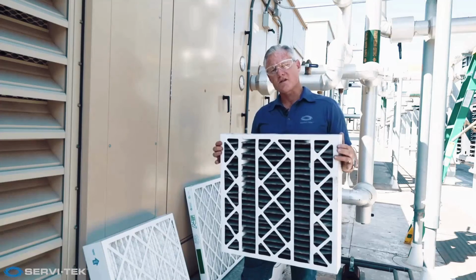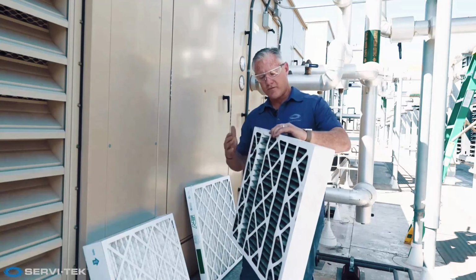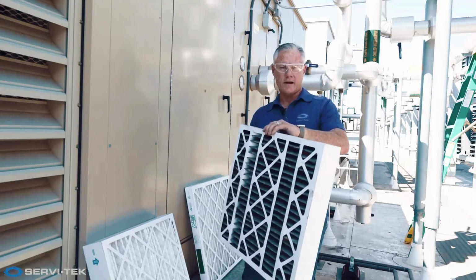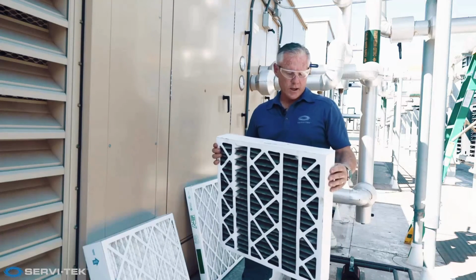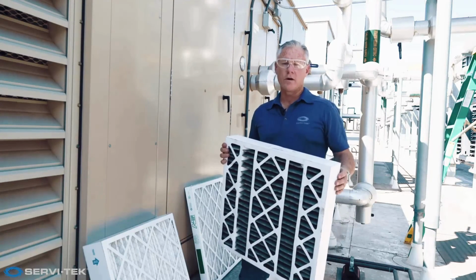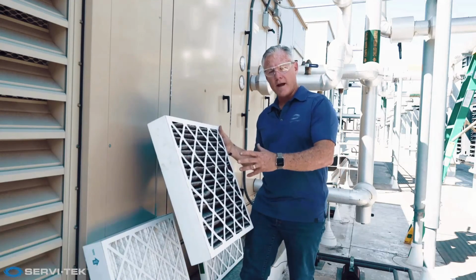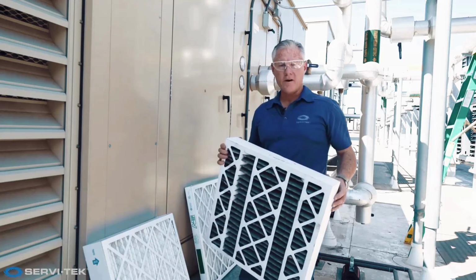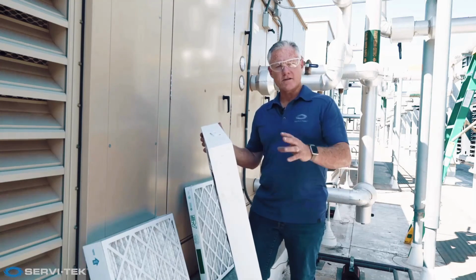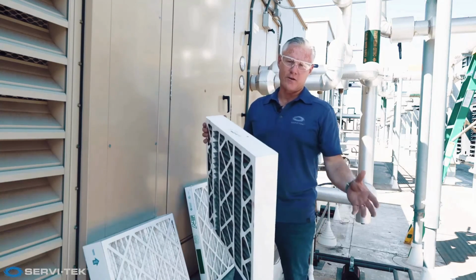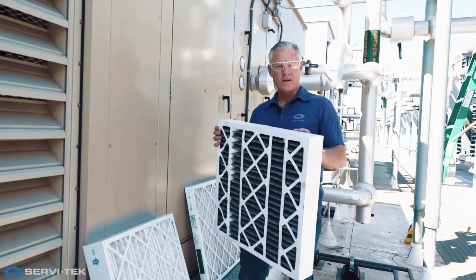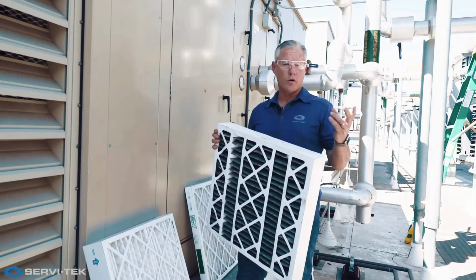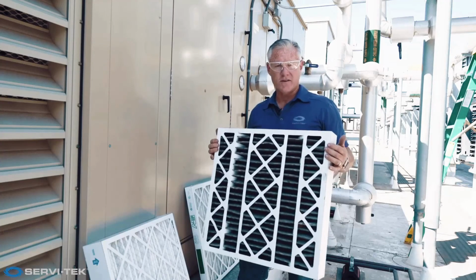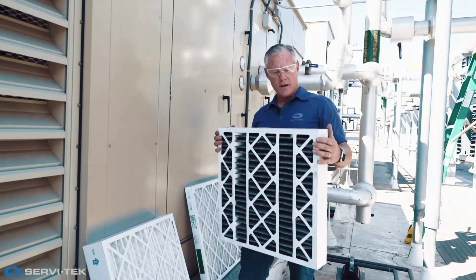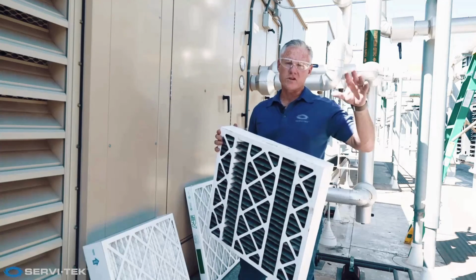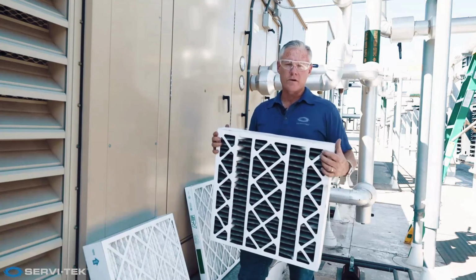Filters should be changed based on their pressure differential. That means the pressure from the inlet side of the filter to the outlet side of the filter. I know a lot of engineers and even property managers will walk into an air handler room, look at the filter, notice it's a little bit gray and say, hey, shouldn't we be changing our filters? Believe it or not, Indoor Air Quality 101 says a dirtier filter actually filters better than a new filter. So one of the main reasons why they're rated at a certain level, in this case a 1/4 inch of water column, before we change this filter, is because that's the efficiency level, not only on the filter medium, but before we start to really draw higher amperage on the motor by creating more resistance, pulling the air through the filter.